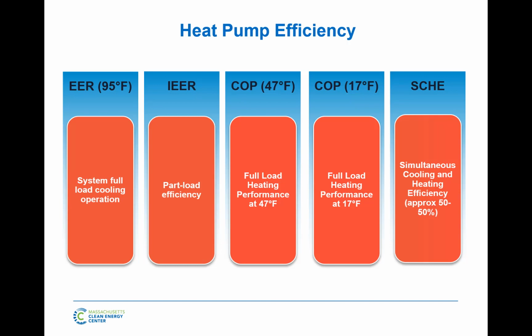Now, I'll use this as a way to talk about how IEER in our minds is already a little outdated. What I mean by that is that it's 9 years old. So IEER, even though it looks at how well you do at 100% load, 75% load, 50%, and 25%, the technology's gone beyond that. 9 years, right? As you can see, in the past 5 years, and I refer to it as cruise control, the VRF manufacturers have really looked into optimizing cruise control.